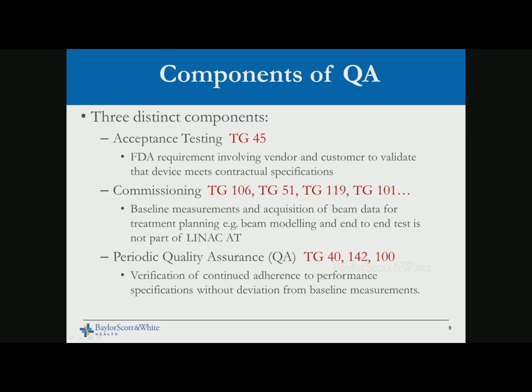The components of QA involve three phases: acceptance testing, commissioning, and periodic quality assurance. Acceptance testing involves vendor and customer validating that the device meets contractual specifications. Commissioning comes after, with some overlap — it includes baseline measurement, beam data acquisition, beam modeling, and end-to-end testing. Periodic QA verifies there is no deviation from the baseline established during commissioning — what we do in daily, monthly, and annual quality assurance.